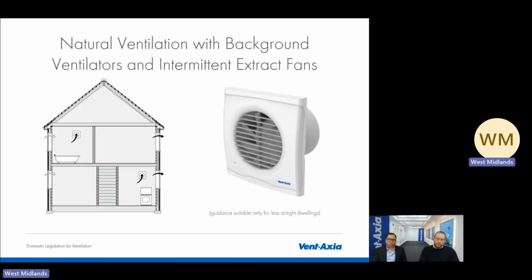Natural ventilation with background ventilators and intermittent extract fans, which is suitable for less airtight dwellings, formerly known as System 1. Intermittent extract fans should be fitted in all wet rooms with correctly sized background ventilators, also known as trickle vents.